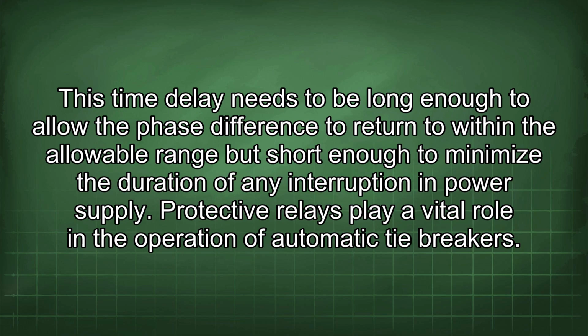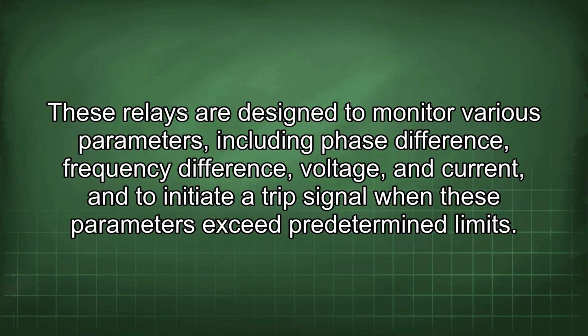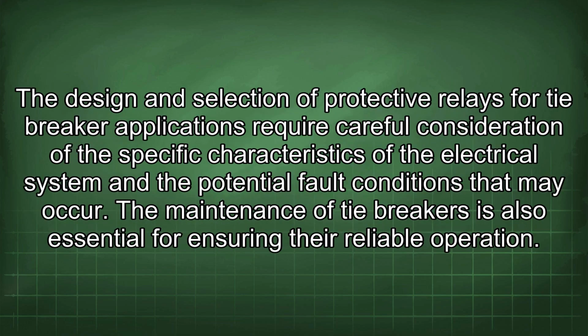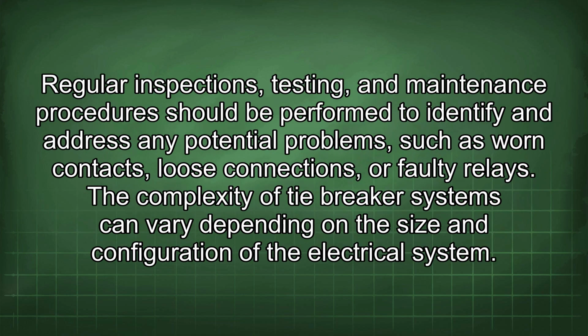Protective relays play a vital role in the operation of automatic tiebreakers. These relays are designed to monitor various parameters, including phase difference, frequency difference, voltage, and current, and to initiate a trip signal when these parameters exceed predetermined limits. The design and selection of protective relays for tiebreaker applications require careful consideration of the specific characteristics of the electrical system and the potential fault conditions that may occur. The maintenance of tiebreakers is also essential for ensuring their reliable operation. Regular inspections, testing, and maintenance procedures should be performed to identify and address any potential problems, such as worn contacts, loose connections, or faulty relays.